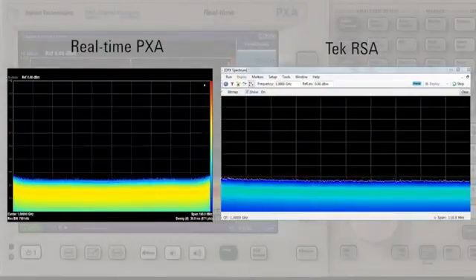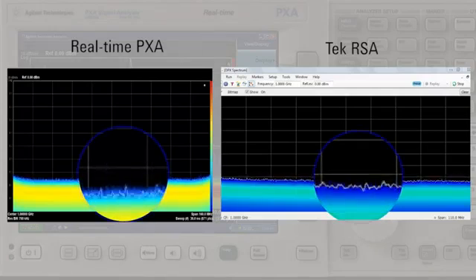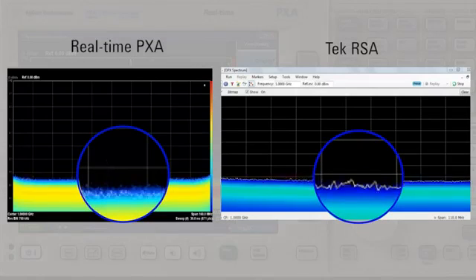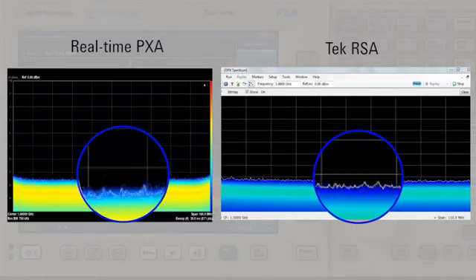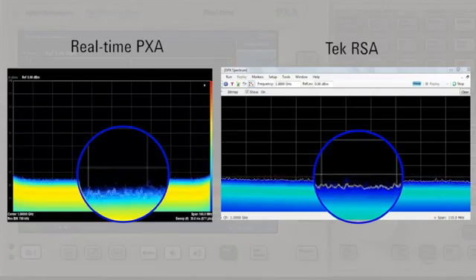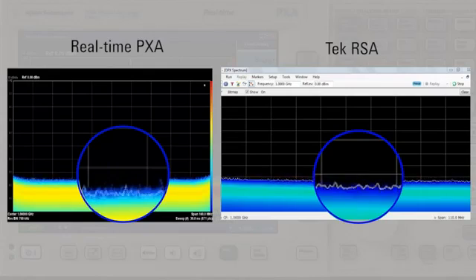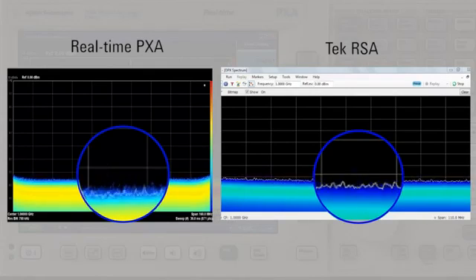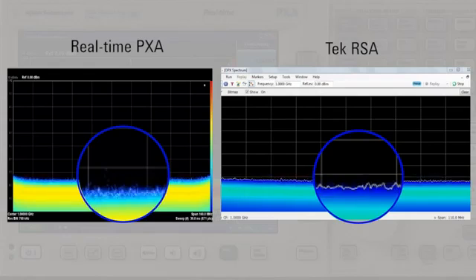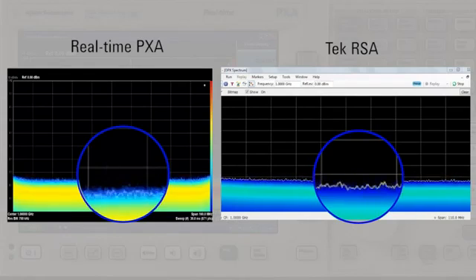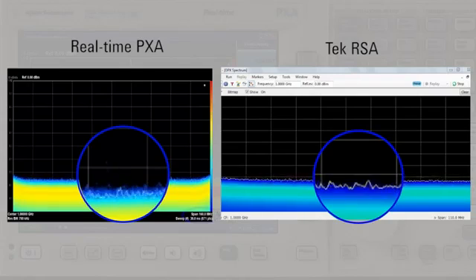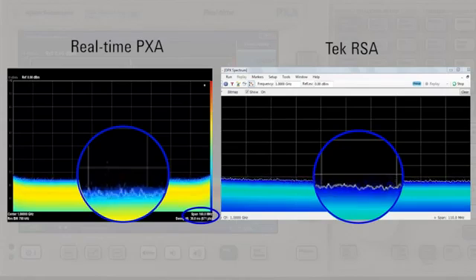The probability of detecting a signal is a function of multiple things. One factor is how much power the signal of interest has in relationship to a threshold, or in this case the noise floor. This is why the instrument's raw noise performance becomes important for detecting intermittent signals. The PXA has approximately 5 dB better noise performance here. It also has the widest real-time bandwidth and a higher sample rate which also improves its probability of intercept. The PXA is doing a much better job of catching the signal every second.